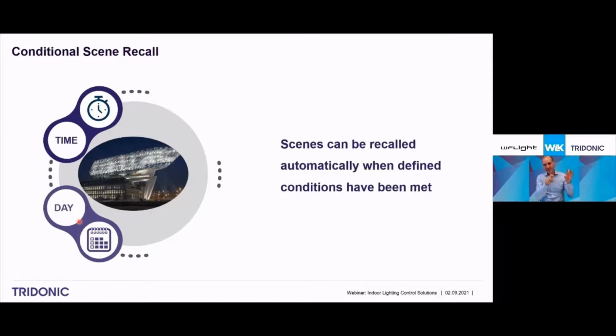So the condition for the luminaires in the corridor is: if there is presence in one of the offices, there should be light in the corridor. Only if there is no presence in the corridor and no presence in any of the single offices can the corridor plus offices shut down the luminaires. You can set a lot of quite advanced things with such simple if-this-then-that conditions and linking.